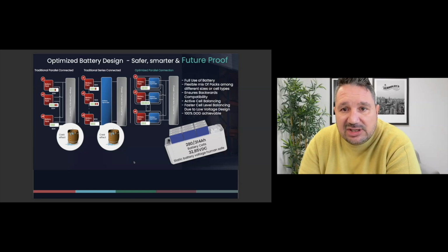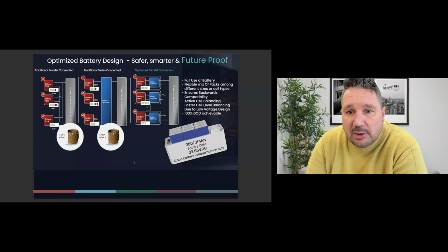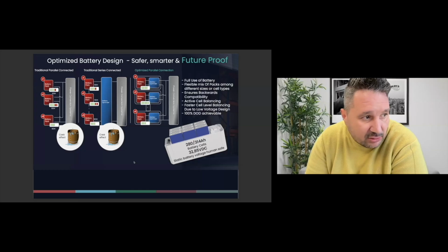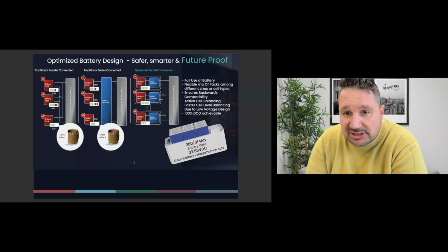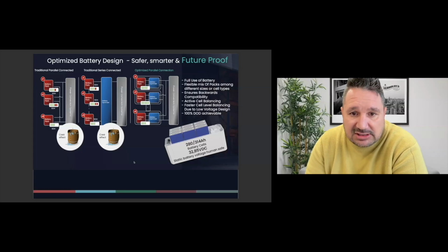With the energy system, each battery is on an island by itself, which means each one of them operates individually. This means that in the future, if you need to replace a battery or add another battery, it doesn't matter if the new cells in the battery came from a different supplier and the capacity is different. You can add it at any state of charge and any state of health, and the system will manage that battery by itself. This also means that if you should have a failure, you only have an isolation of a single battery module. This then makes sure that the rest of the battery system is always working, and you only lose whatever that battery size is on your outage.